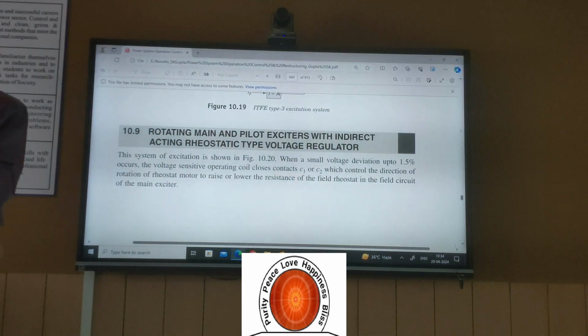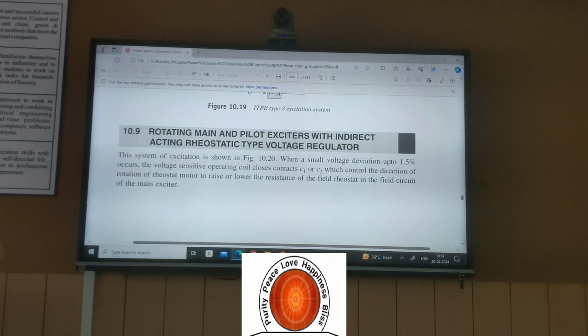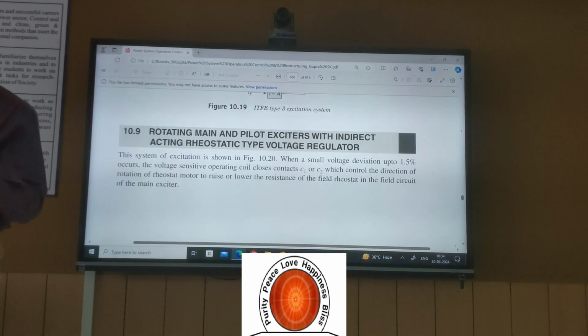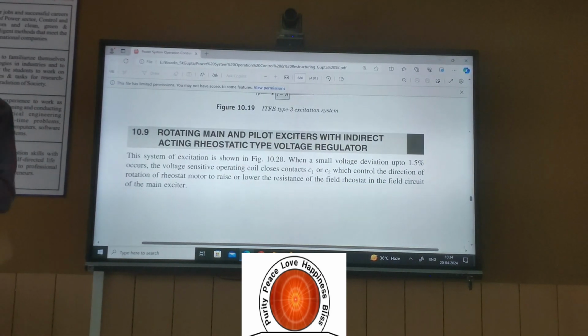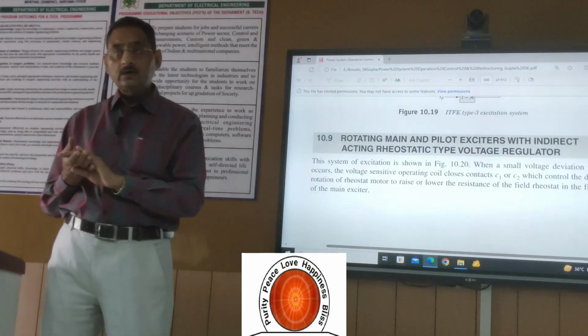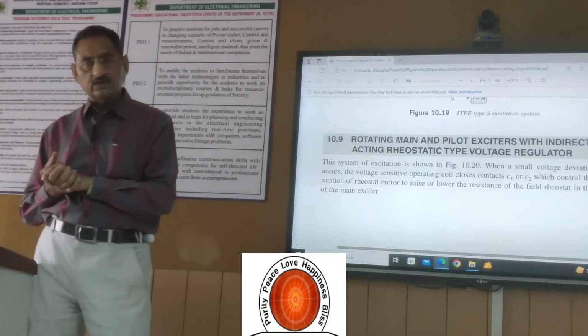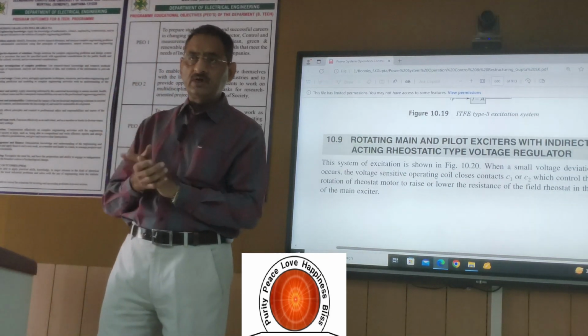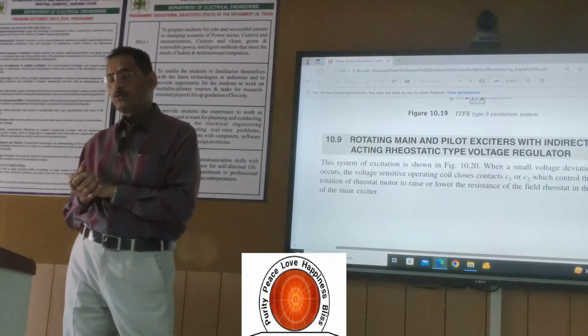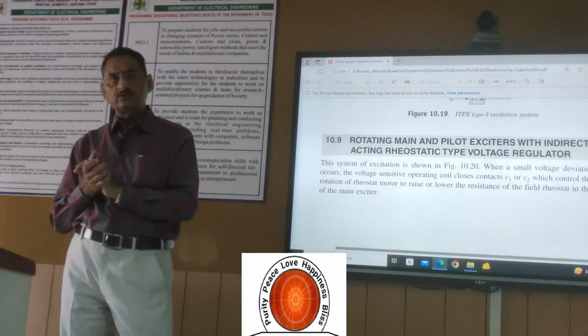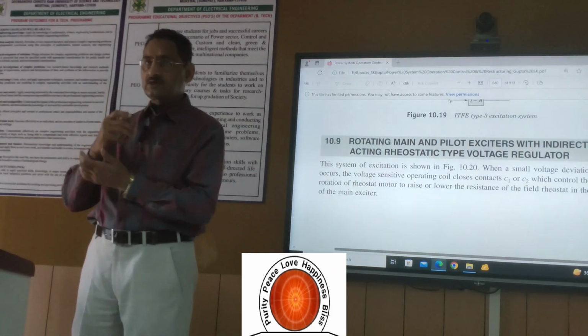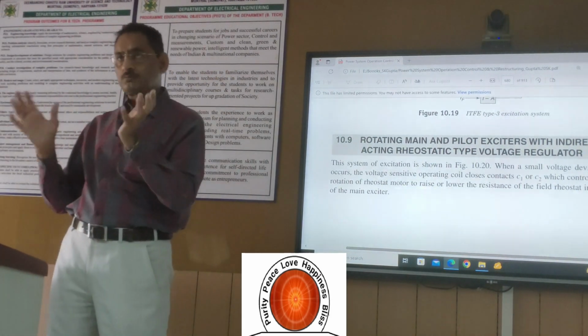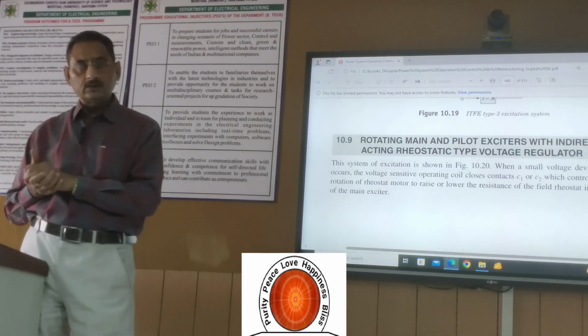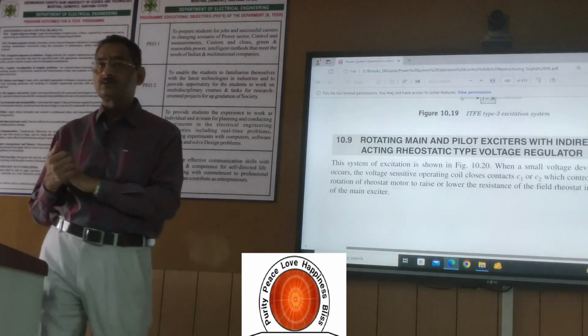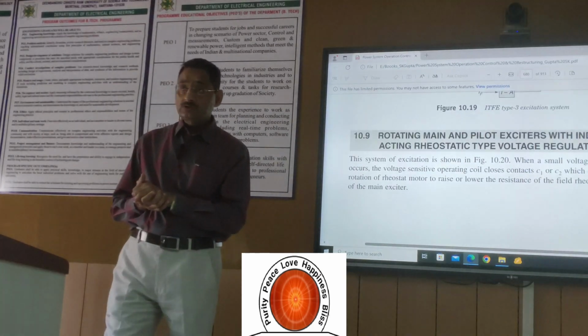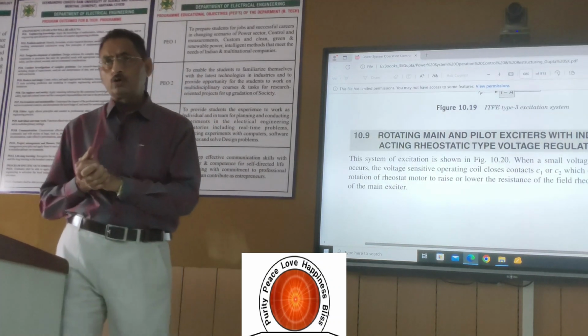In the previous one we have seen that the exciter is a DC generator, which is self-excited. Now, say 100 MVA synchronous generators are there. Just to supply the field current to 100 MVA, if we consider 1% or less than 1% of the power, for example 1%, then the size of the DC exciter can be 1 megawatt. Even if it is 0.1%, then 100 kW. A 100 kW DC generator is big enough, and that exciter is working at a low voltage.